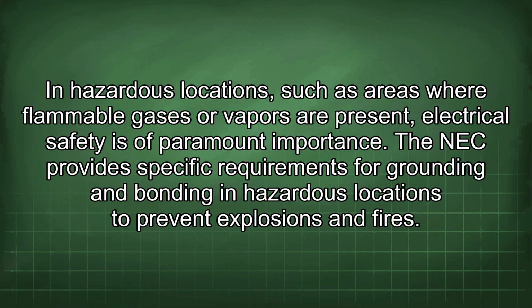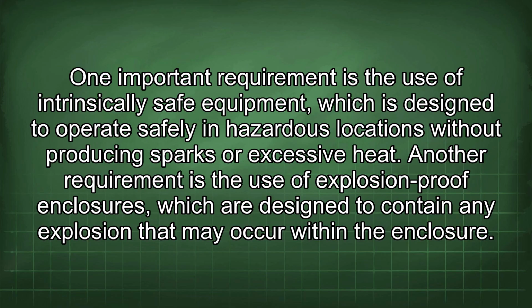In hazardous locations, such as areas where flammable gases or vapors are present, electrical safety is of paramount importance. The NEC provides specific requirements for grounding and bonding in hazardous locations to prevent explosions and fires. One important requirement is the use of intrinsically safe equipment, which is designed to operate safely in hazardous locations without producing sparks or excessive heat. Another requirement is the use of explosion-proof enclosures, which are designed to contain any explosion that may occur within the enclosure.